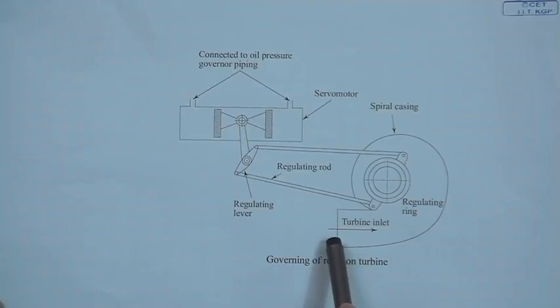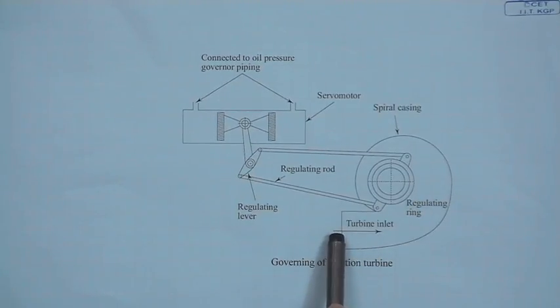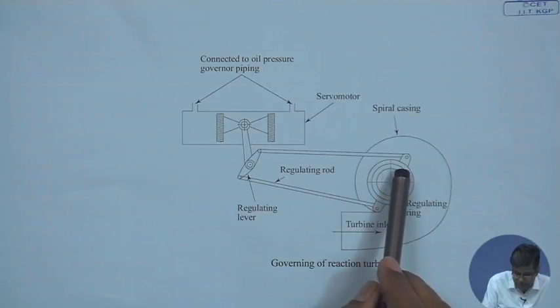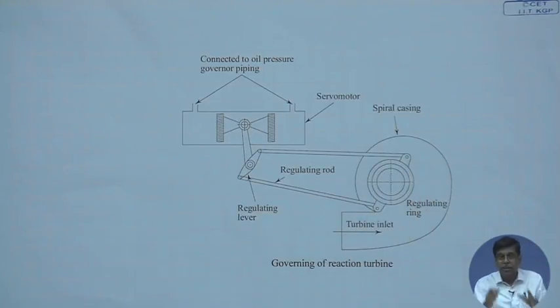In a reaction turbine, water enters the scroll casing or volute. From the scroll casing, the flow meets the stay vanes and the wicket gates. These wicket gates are guide vanes pivoted at a point; they can be rotated or swivelled about this pivotal point to change the passage area through which the fluid flows. By changing this area, the fluid flow rate is adjusted. The pivotal point is the main point of the wicket gate or guide vanes.